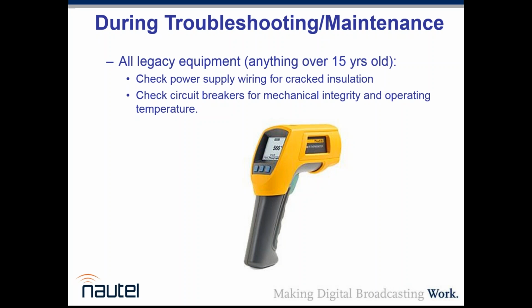It wouldn't hurt to also aim it at the places where the AC feed comes into your transmitter and connects to the lugs. Same exact issue applies anywhere you've got a compression connection, whether it's a lug, a bolt-down connection, or even a crimp lug. Unless you had the specific crimp tool at the time, there'll be some error in there.